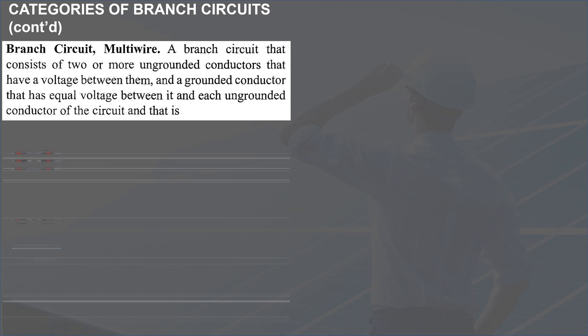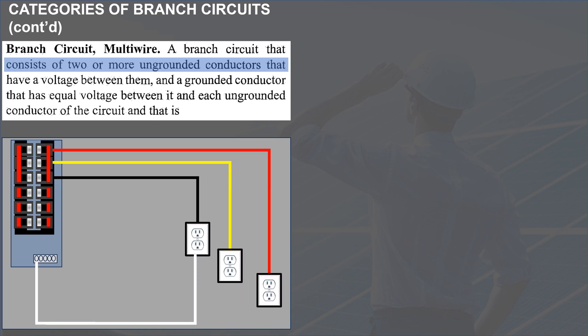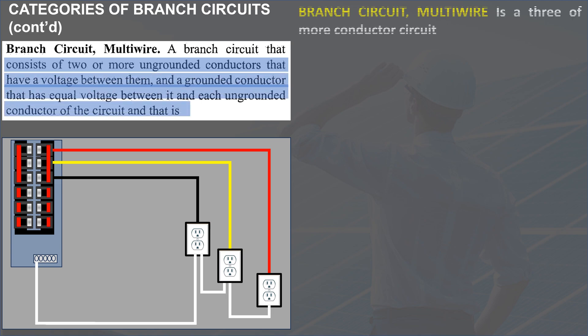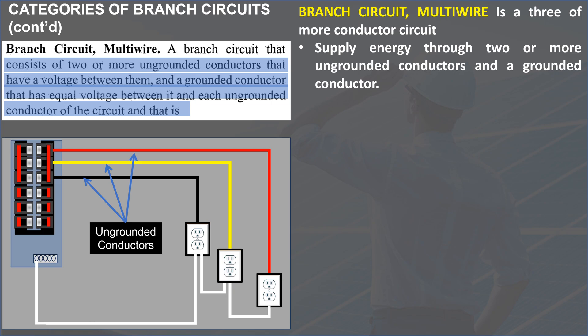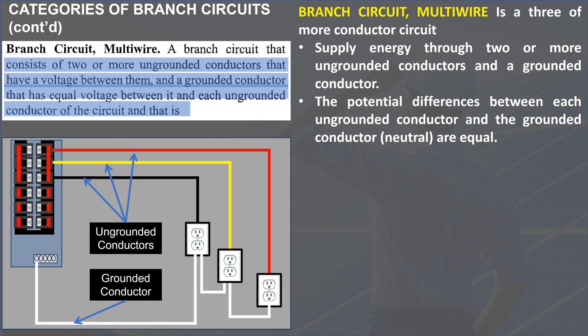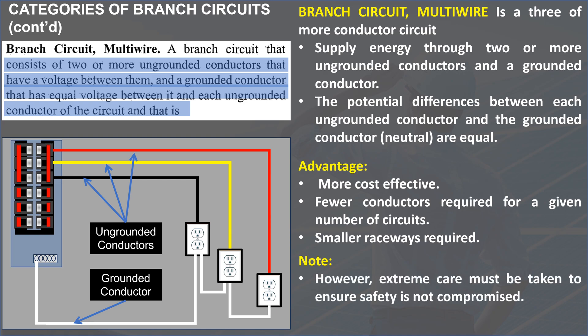Lastly, branch circuit multi-wire: a branch circuit that consists of two or more ungrounded conductors that have a voltage between them, and a grounded conductor that has an equal voltage between it and each ungrounded conductor of the circuit. Therefore, a branch circuit multi-wire is a three or more conductor circuit that supplies energy through two or more ungrounded conductors and a grounded conductor. The potential differences between each ungrounded conductor and the grounded conductor are equal. Multi-wire branch circuit has a big advantage: the cost is more effective because fewer conductors are required and raceways will be smaller. However, extreme care must be taken to ensure safety is not compromised.